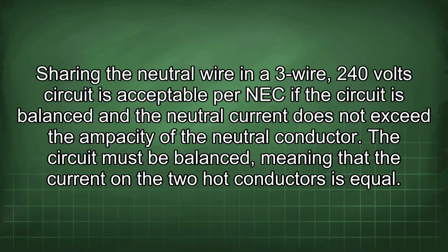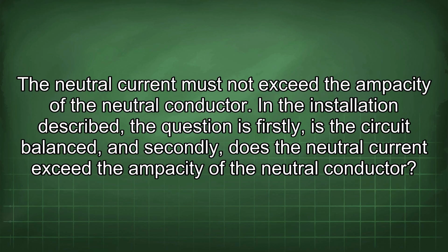Sharing the neutral wire in a 3-wire, 240-volt circuit is acceptable per NEC if the circuit is balanced and the neutral current does not exceed the ampacity of the neutral conductor. The circuit must be balanced, meaning that the current on the two hot conductors is equal. The neutral current must not exceed the ampacity of the neutral conductor. In the installation described, the question is firstly, is the circuit balanced, and secondly, does the neutral current exceed the ampacity of the neutral conductor?